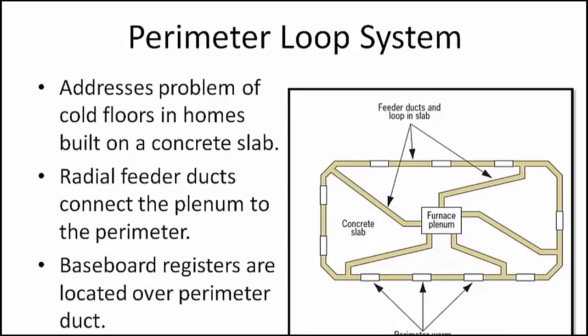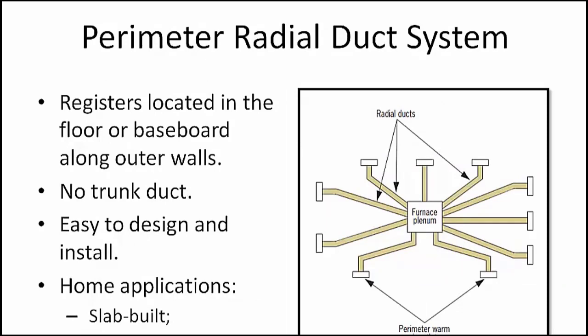The perimeter loop duct arrangement, as shown here, addresses the problem of cold floors in winter in a house built on a concrete slab directly laid on the ground. Warm air is directed downward from the furnace, which usually sits on the ground floor, to a subfloor plenum. Radial feeder ducts lead from the plenum to the perimeter ductwork, and all of the ducts are embedded in the concrete slab. In winter, the warm air flowing in the duct keeps the floor warm. The baseboard registers are located directly over the perimeter duct along the outer walls or in the floor next to the walls, and warm air is discharged upward into the rooms. The same ducts can be successfully adapted to summer cooling.